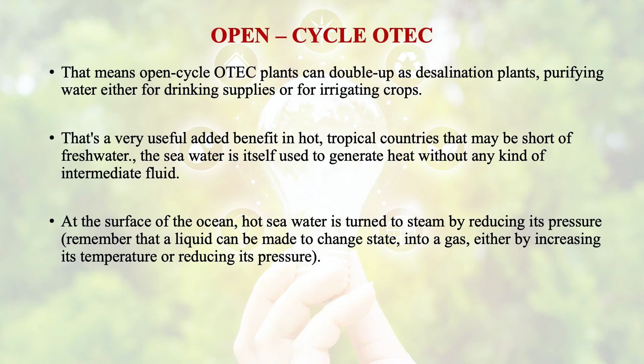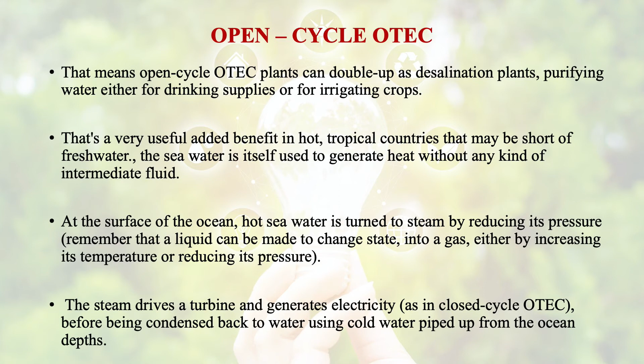The seawater is itself used to generate heat without any kind of intermediate fluid. At the surface of the ocean, hot seawater is turned to steam by reducing its pressure. The steam drives a turbine and generates electricity as in closed cycle ocean thermal energy conversion, before being condensed back to water using cold water piped up from the ocean depth. One of the very interesting byproducts of this method is that heating and condensing seawater removes the salt and other impurities so that the water is pure and salt-free.